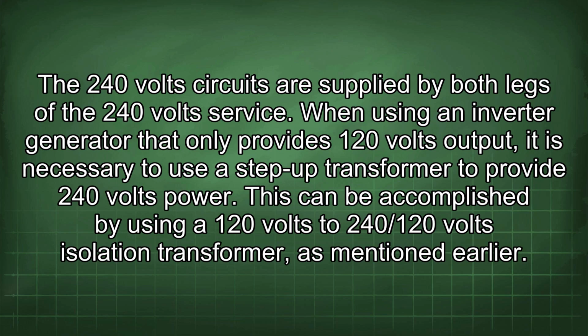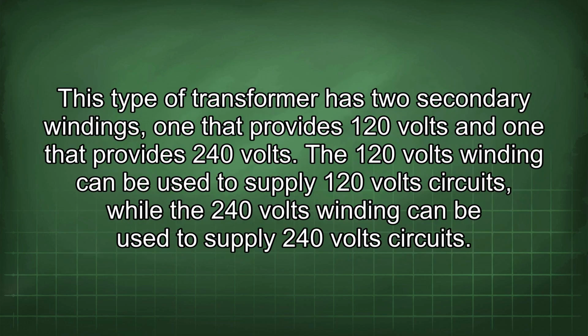When using an inverter generator that only provides 120 volts output, it is necessary to use a step-up transformer to provide 240 volts power. This can be accomplished by using a 120 volts to 240/120 volts isolation transformer, as mentioned earlier. This type of transformer has two secondary windings, one that provides 120 volts and one that provides 240 volts. The 120 volts winding can be used to supply 120 volt circuits, while the 240 volts winding can be used to supply 240 volt circuits.